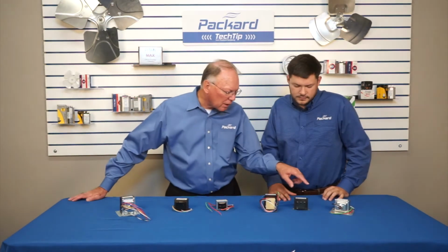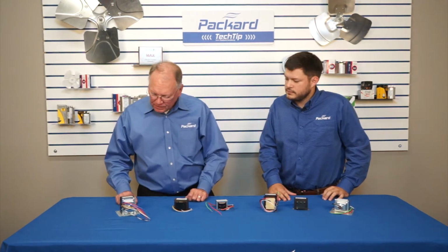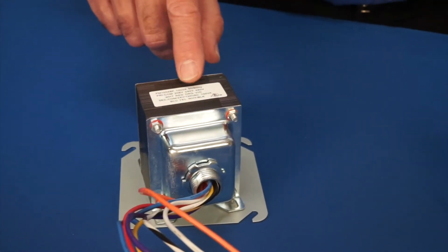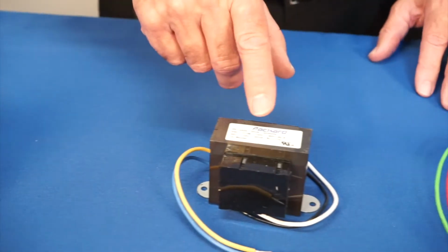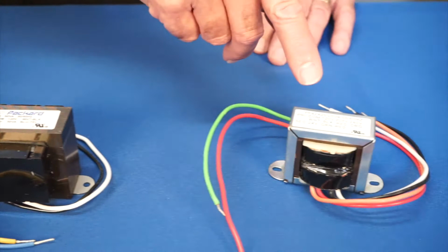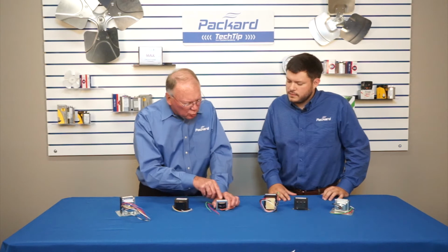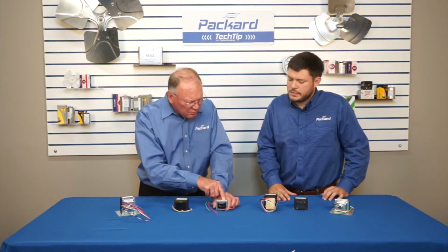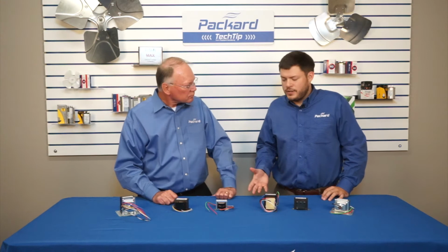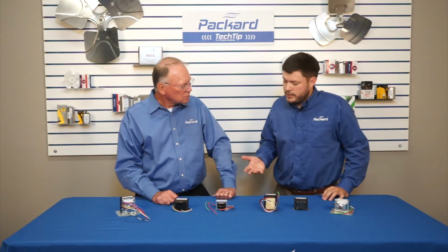Now, I notice on a lot of these, they have different voltages. So this one says 208, 240, 480. This one says 120. This one says 120, 208, 240. Does that mean, because this one says 120, 208, 240, my application has to have all three of those voltages available for this? Of course not, no. Transformers are typically designed to hit more than one target application. Therefore, you stock one and you can apply that across multiple situations.